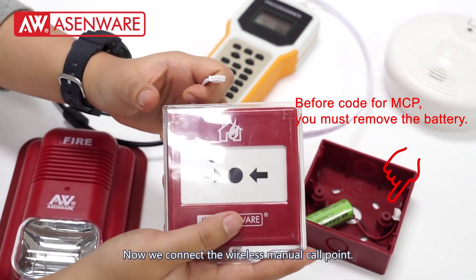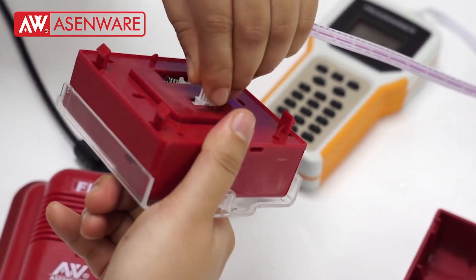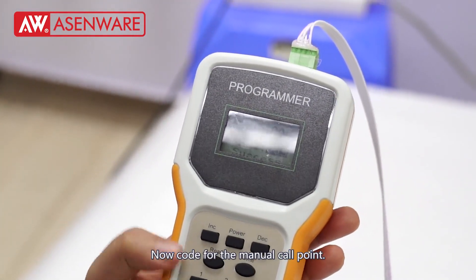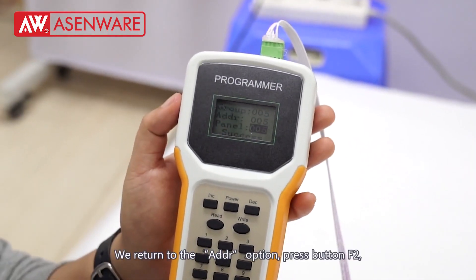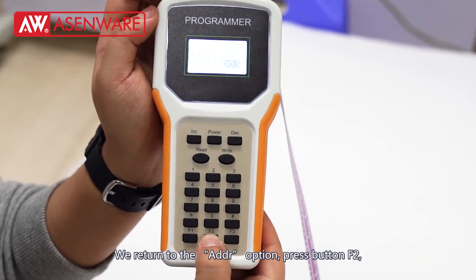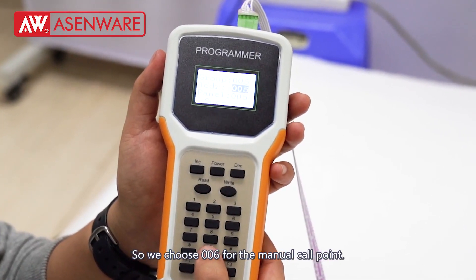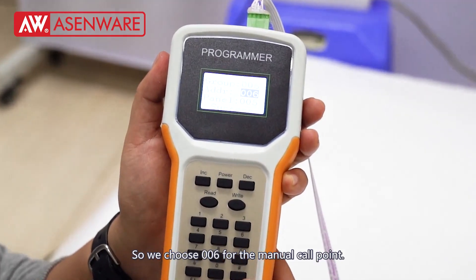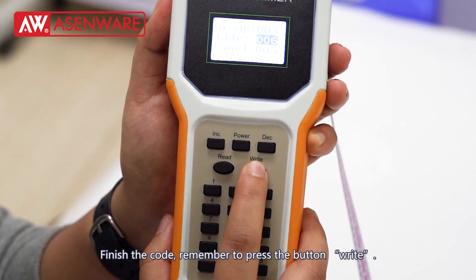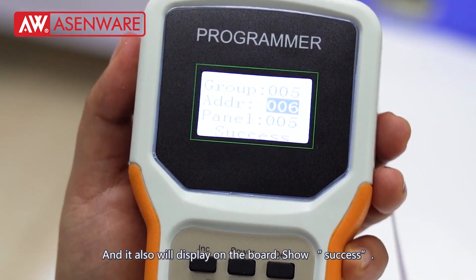Now we connect the wireless manual call point. Code for the manual call point. We return to the Addr option and press button F2. Remember, the address cannot be the same one, so we chose 006 for the manual call point. Finish the code, remember to press the Write button, and it will also display success.